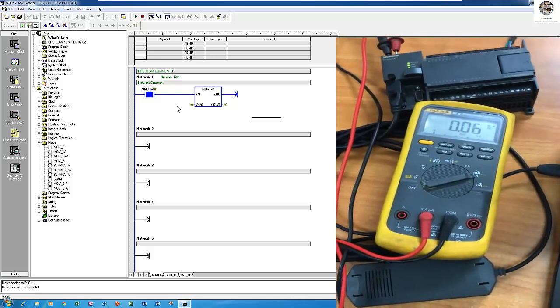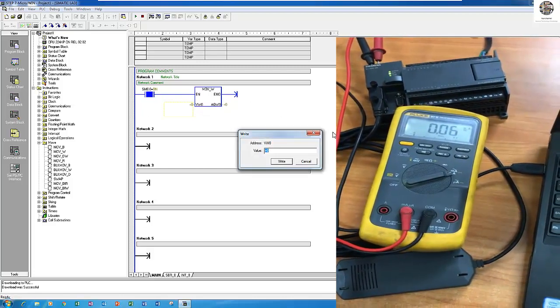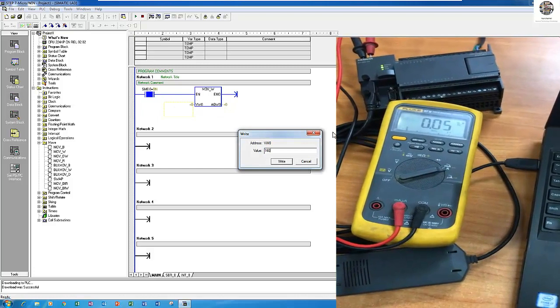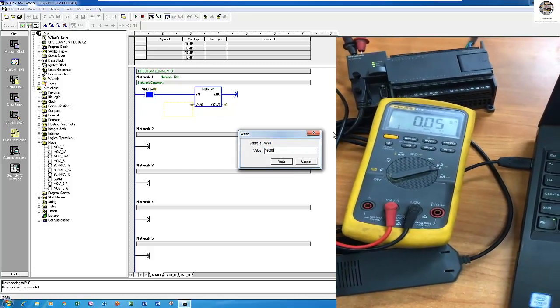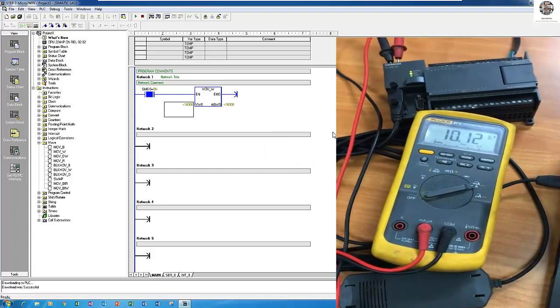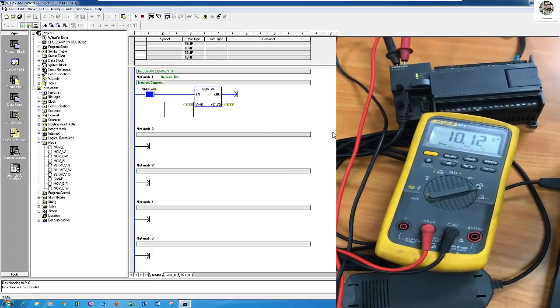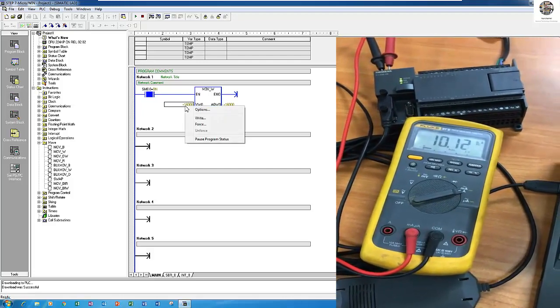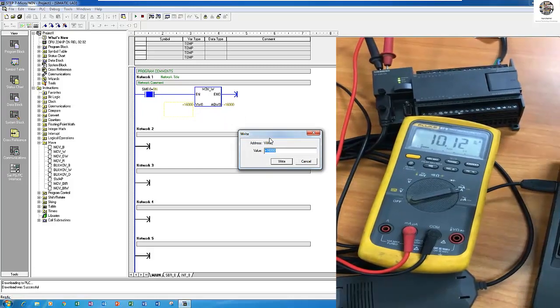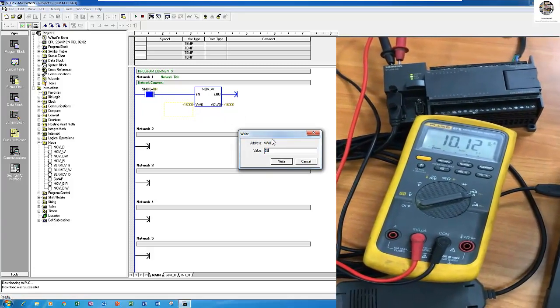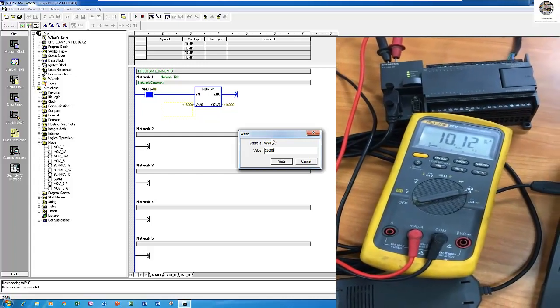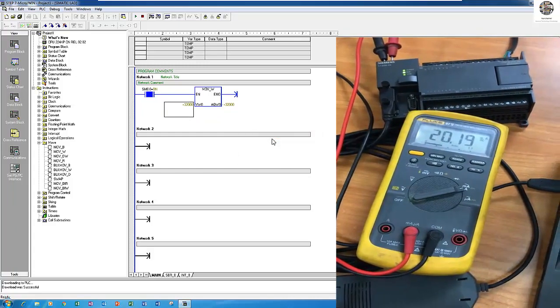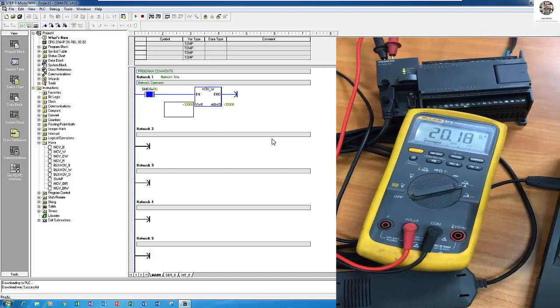Right now it's 0 milliamp. I will edit something. For example 16,000. 16,000 is approximately 10 milliamp. I will increase to maximum 32,000. The milliamp is 20 milliamp. Right.